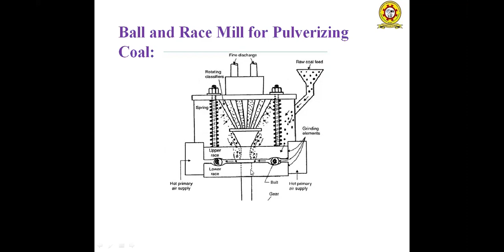And the next one is the ball mill. This is the diagram of the ball mill, which is used to prepare coal for the combustion process. In the ball mill, the raw feed material enters here. There are grinding balls made of iron, and they are very heavy. The feed material is entered from both sides. When the feed material enters this mill, the grinding balls rotate. These are the grinding balls, and this yellow is the coal. When they rotate, the raw coal is crushed into fine particles.